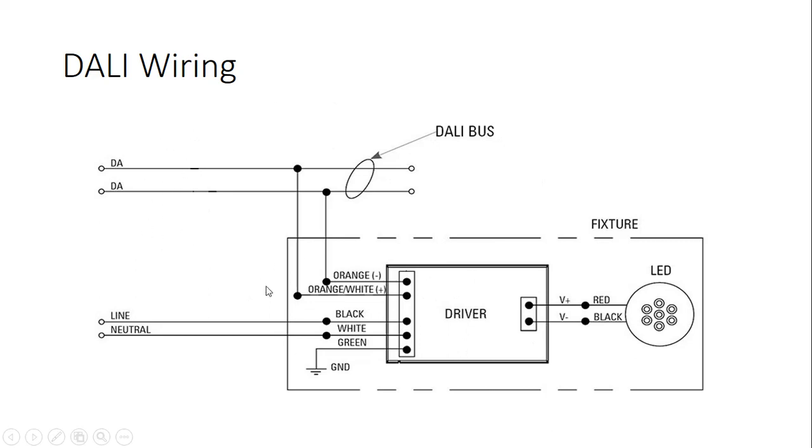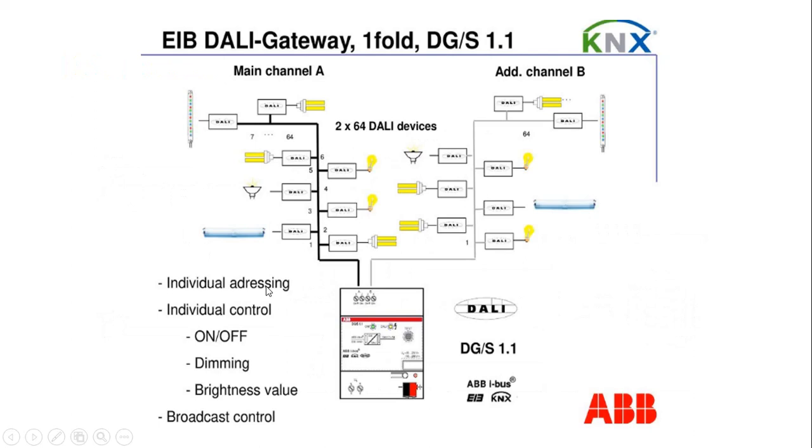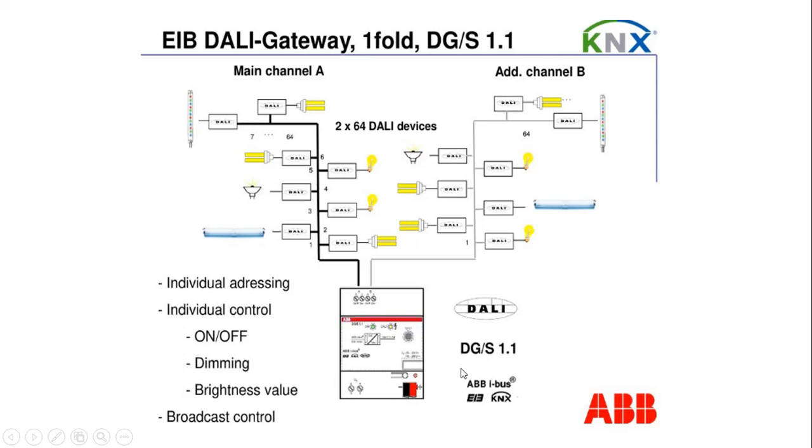The next step, I will show you how we connect this with KNX. So fitting one, then there will be fitting two, fitting three, fitting four, and maximum up to 64. Then the DALI cable is coming into our KNX device DALI device. So channel one is connected here and this is a two channel DALI gateway, ABB two channel DALI gateway. You can connect two different channels, so this one you will have 64 lights you can connect here and then 64 you can connect here, maximum 64 lights.